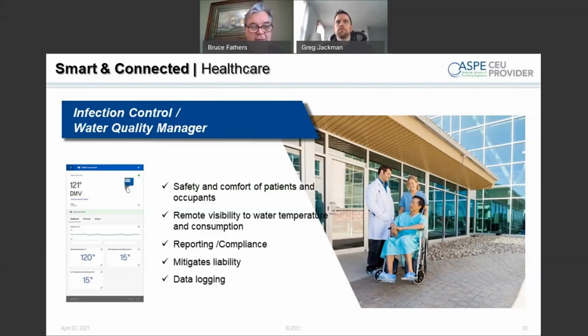Well, it may tell you that if you ran a report or looked at the data, you may see that, let's say, your hot water pressure is spiking. You can say, okay, my hot water for whatever reason is spiking at this particular time, or my hot water incoming temperature is dropping. I'm talking about incoming pressure and temperature. So there are things you'll be able to look at that help you diagnose what's going on.